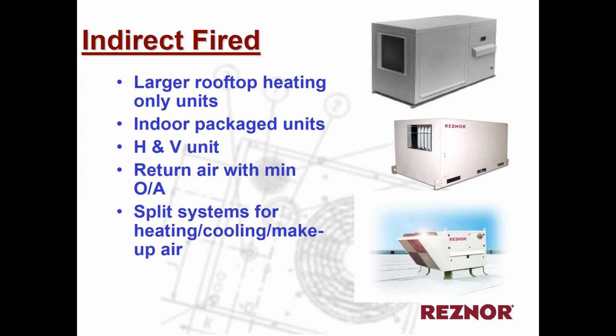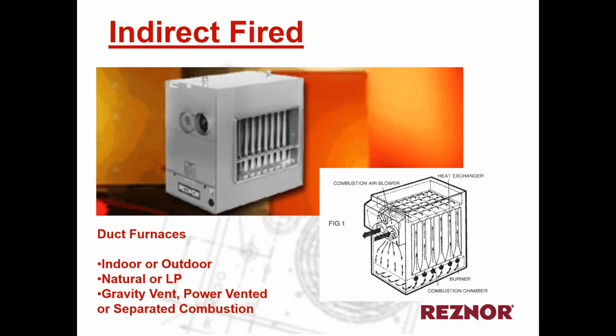Now, most of our product is indirect fired, meaning that we have a heat exchanger in between the airflow and the combustion side of the appliance. We do make some direct fired, and we're going to talk about that in a little bit. But for the most part, most of our product is indirect fired. That's what our unit heaters are. You'll see here, this is our packaged heating equipment, which is indirect fired. We can make them in a rooftop configuration, an indoor packaged configuration, a heating and ventilating unit. So in other words, it's going to use some return air and some outside air. And we also make large split system units for heating, cooling, and dehumidification of makeup air. And typically they're going to be indirect fired as well.